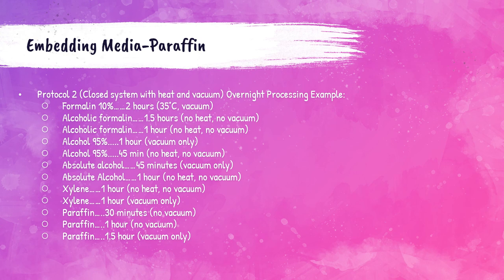Protocol two is a closed system with heat and vacuum. The tissue is placed in 10% formalin for two hours at 35 degrees Celsius with vacuum, then an hour and a half of alcoholic formalin with no heat or vacuum, then one hour of alcoholic formalin with no heat or vacuum. Then one hour of 95% alcohol with vacuum only, 45 minutes of 95% alcohol with no heat or vacuum, 45 minutes of absolute alcohol with vacuum, one hour of absolute alcohol with no heat or vacuum, one hour of xylene with no heat or vacuum, one hour of xylene with vacuum. Then 30 minutes of paraffin with no vacuum, one hour of paraffin with no vacuum, and one and a half hours of paraffin with vacuum.